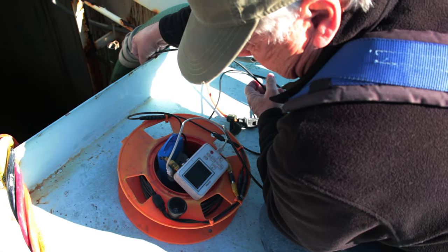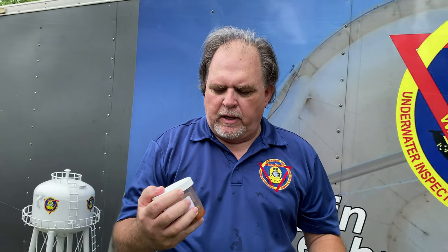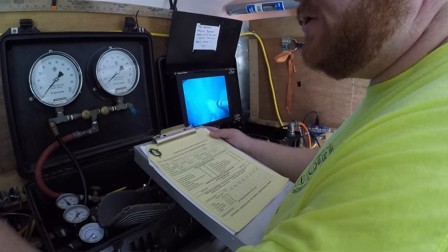It's very important that this stuff can live in the bottom of a tank undetected and unknown. Because when they do a water test, they're testing the water three feet off the tank floor. So when we take a sample of sediment, then they can really see what's going on. Some of our customers have found everything you can imagine in the tank sediment. The EPA has written papers about it. There's always this war going on — the treatment chemicals versus whatever's growing in the tank sediment.